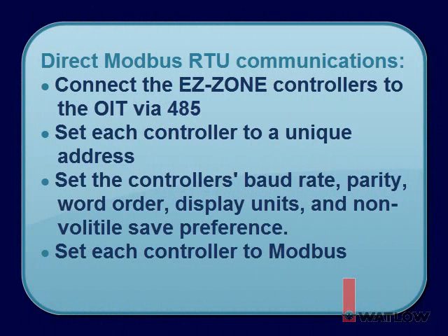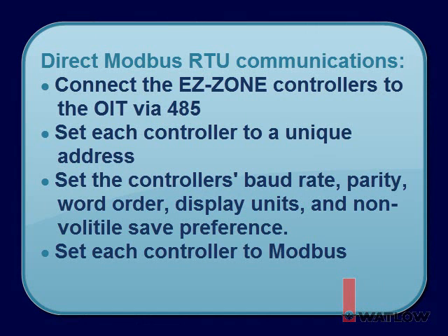Let's review. To set up Modbus RTU communications directly between a Silver Series OIT and EZ-ZONE RM controllers, you must connect the EZ-ZONE RM controllers to the OIT via a 485 network, set each RM module to a unique address. With the RM set to Standard Bus Communications, use EZ-ZONE Configurator to set the Modbus RTU settings on the controller's Communications 1 menu, including the baud rate, parity, word order, display units, and non-volatile save preference.